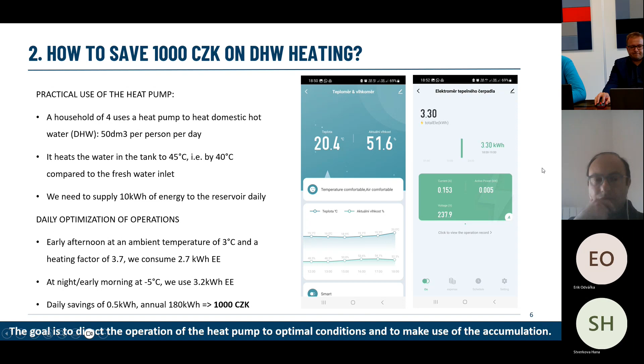And there are lots of systems that actually enable you nowadays to start setting these control rules. But first and foremost, start measuring, start understanding how the installations behave, what the building actually behaves like, and then you can start saving through efficiency. So what you see in the datasheet, in other words, that's the prime scenario. The heat pump doesn't perform defrost. It is relatively dry air outside. It doesn't condense too much water that would freeze into ice. Okay, it yields you these significant coefficients of performance. But in real operation, it could be significantly detrimental compared to what you see in the datasheet.